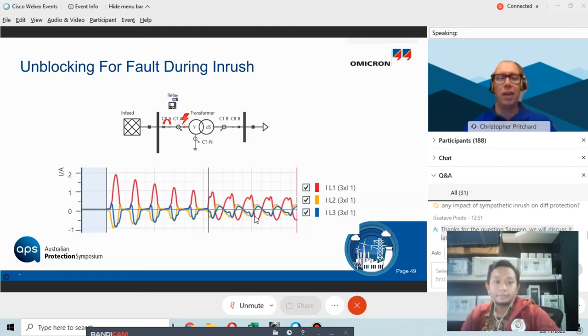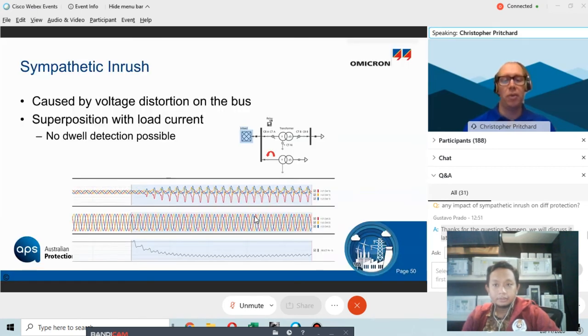Just very quickly, sympathetic inrush is an issue. Maybe not everybody of you encountered this, but some of our customers did. It's usually due to energization of a parallel transformer that is then causing some distortion on the voltage, which is then on the transformer we're actually trying to protect, causing a kind of inrush condition.